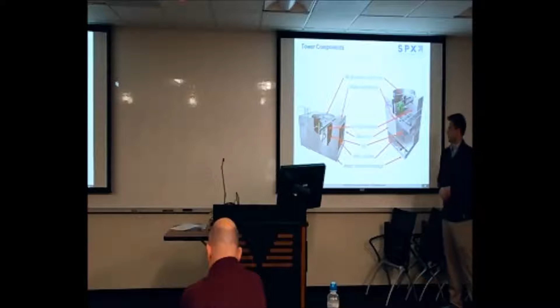The fill here, which is this black PVC mesh-looking material, is really where your thermal transfer is happening. A lot of people consider the fill probably the most important component within the cooling tower. Your fill is where your water comes into contact with your air, cooling the water for the purpose of the system. When you talk about maintenance with fill, it's mostly going to be cleaning and just observing the condition of the fill.